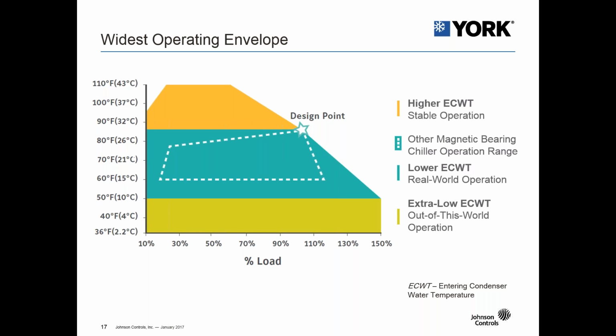And we're also able to use low entering condenser water temperature to improve the efficiency of the total system while utilizing low tower water temperatures that may be available in certain areas of installations throughout the world. And we're also able to utilize extra low entering condenser water temperature, and we're going to touch upon that a little further. So typically on traditional systems, you would see minimum entering condenser water temperatures anywhere from 65 to 55, but now we are able to go well below that.